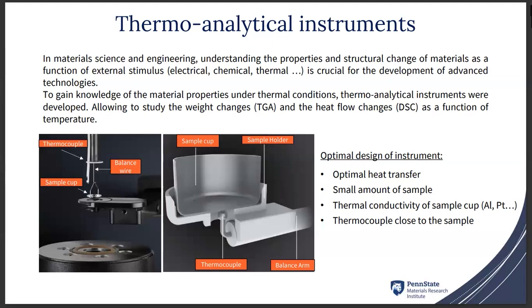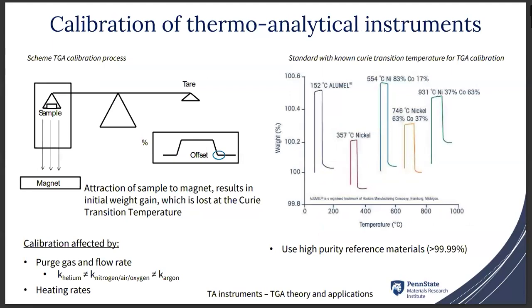And I will just present for the TGA the way the instrument is calibrated. To do the calibration, we need to use a high purity reference material. In the world of TGA, we use different metals or alloys that have very well-defined Curie transition temperature. The Curie transition temperature is the temperature at which the material changes its magnetic property. So we load the sample in the TGA, tare the instrument, and then put a magnet under the sample, which leads to a gain of mass of the sample. Then we do the temperature calibration, and at the Curie temperature, the weight goes back to its initial value, which gives you the actual temperature inside the instrument. So there is no change of sample mass, it's just the change of the property.